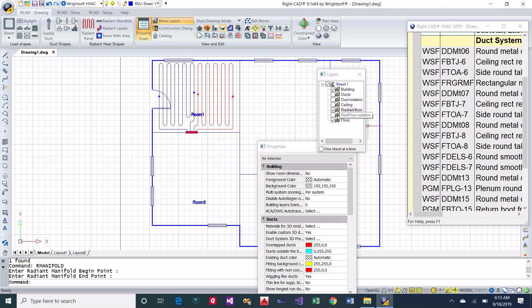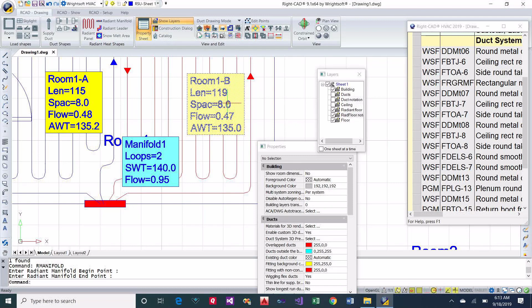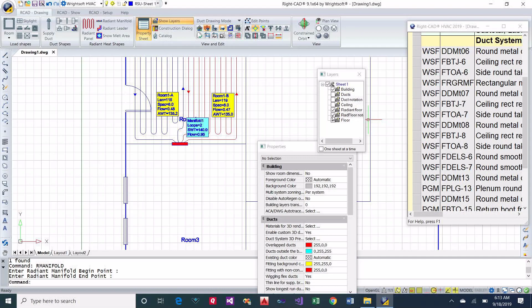This puts things on different layers, so you can easily hide them. The radiant floor notation automatically gives you flow and temperature calculations, because it knows the heating load needed for the room, along with geometry, piping location, and diameters, which let it calculate everything.